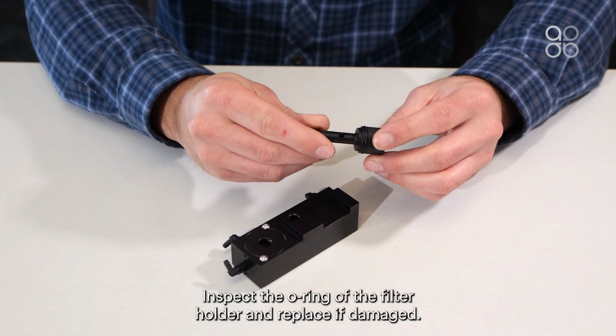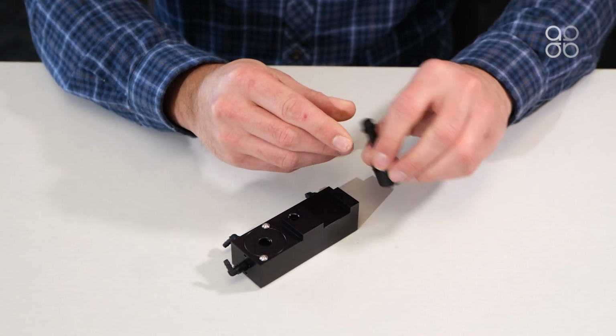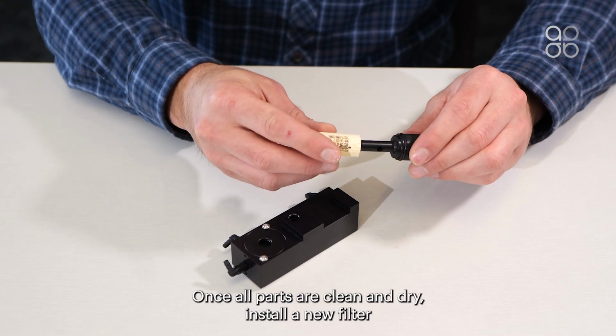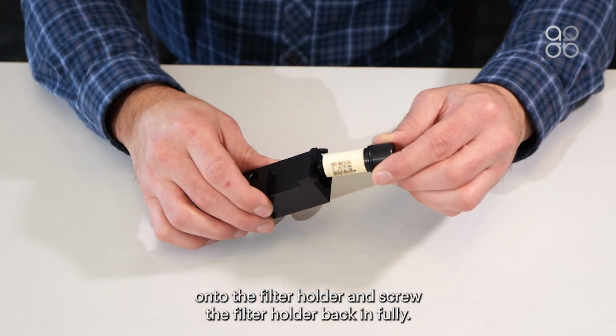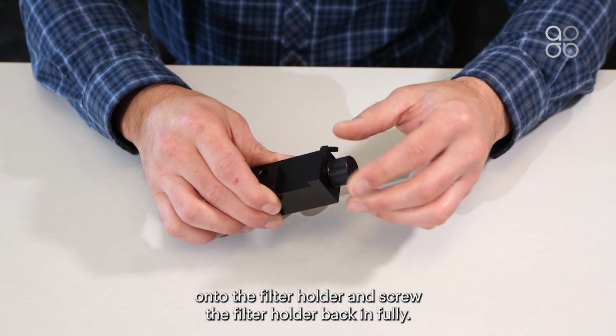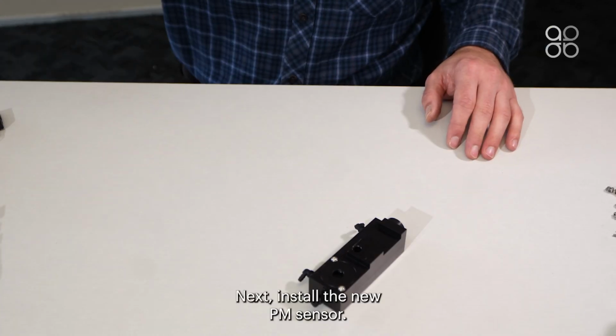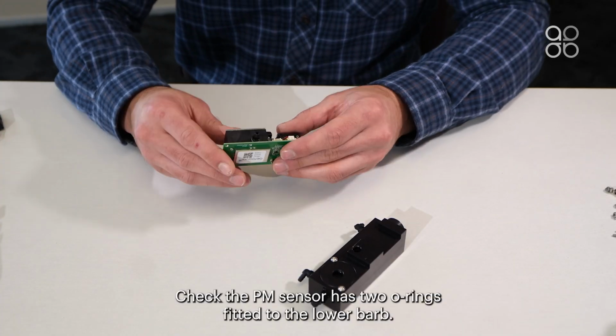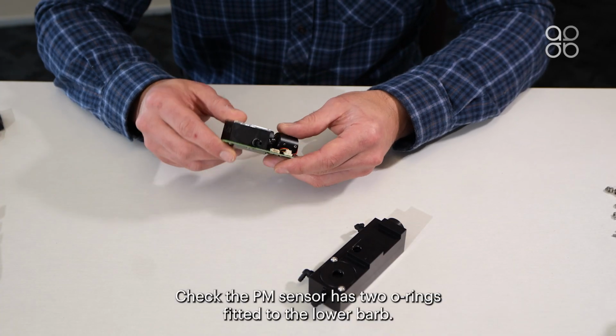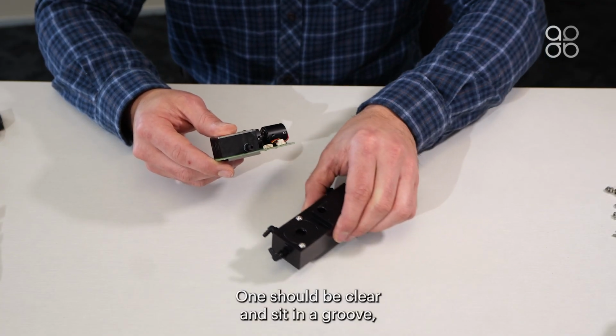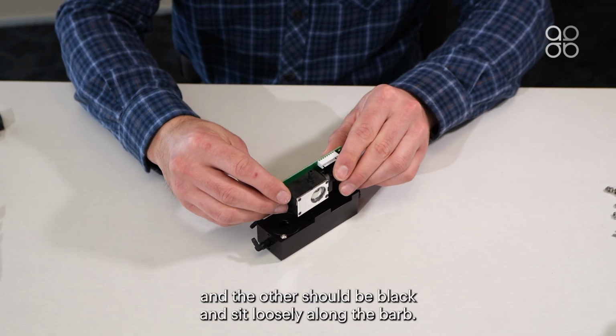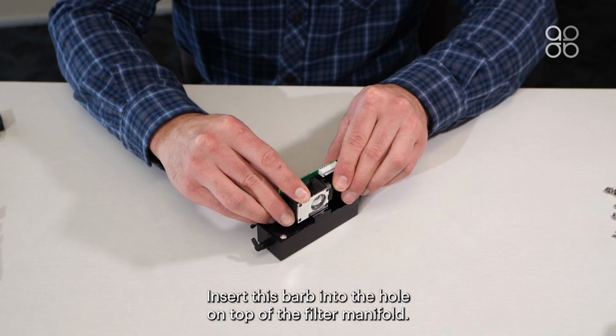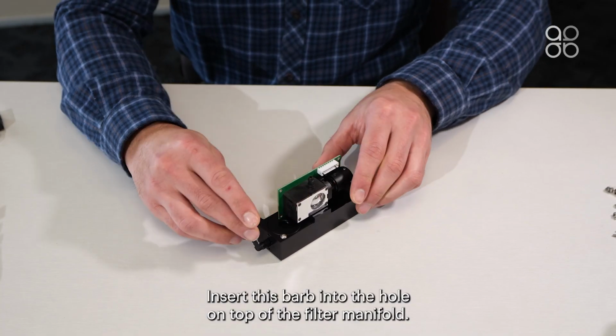Inspect the O-ring of the filter holder and replace if damaged. Once all parts are clean and dry, install a new filter onto the filter holder and screw the filter holder back in fully. Next, install the new PM sensor. Check the PM sensor has 2 O-rings fitted to the lower barb. One should be clear and sit in a groove, and the other should be black and sit loosely along the barb. Insert this barb into the hole on top of the filter manifold.